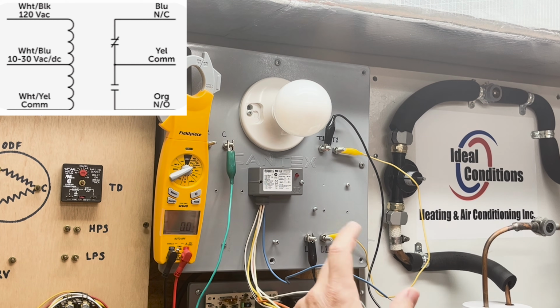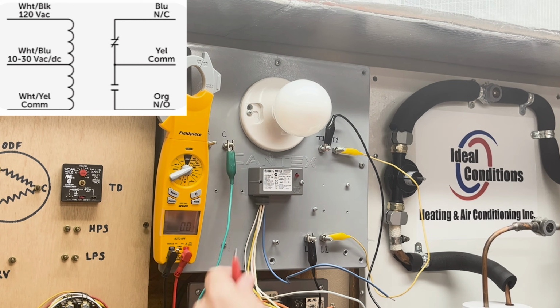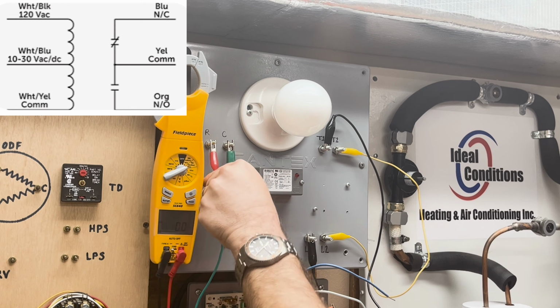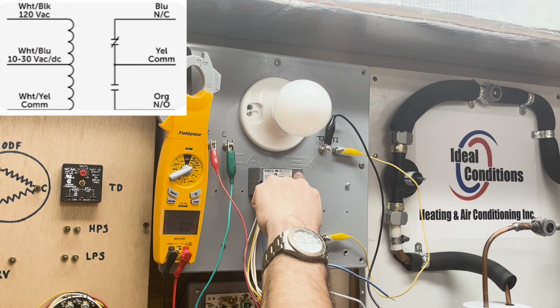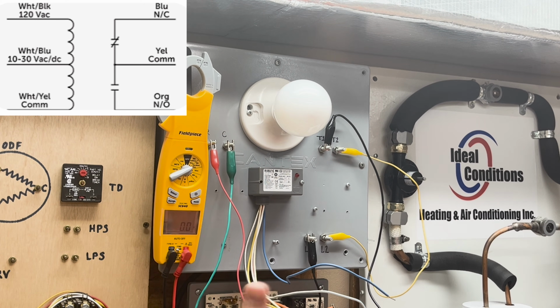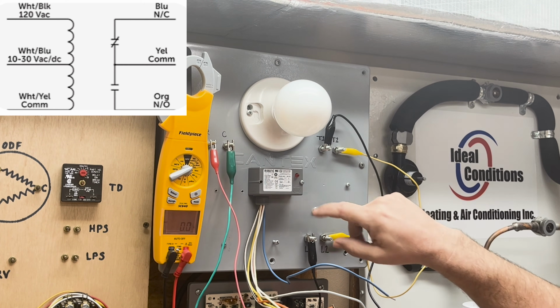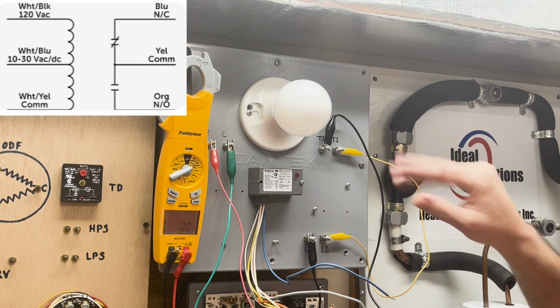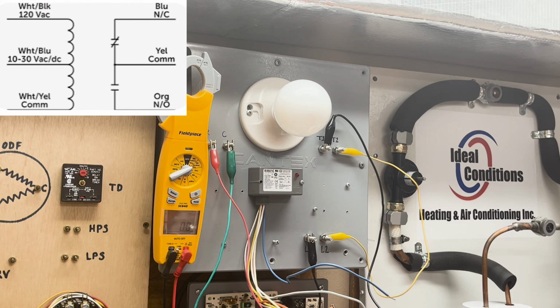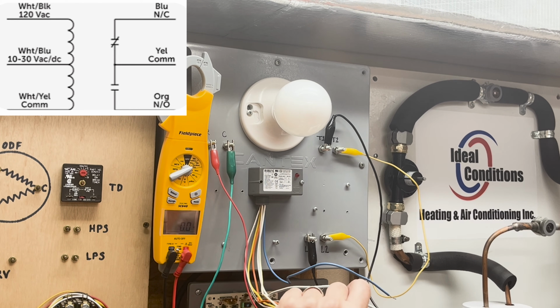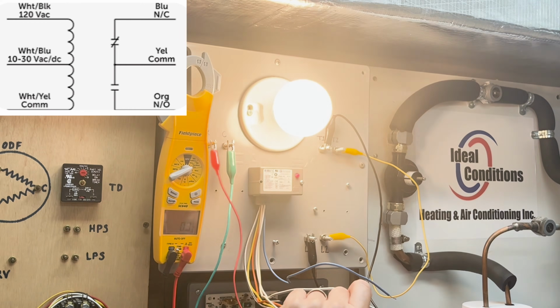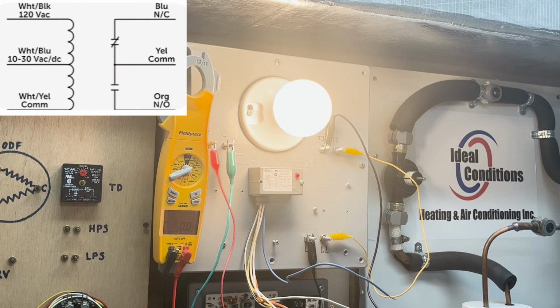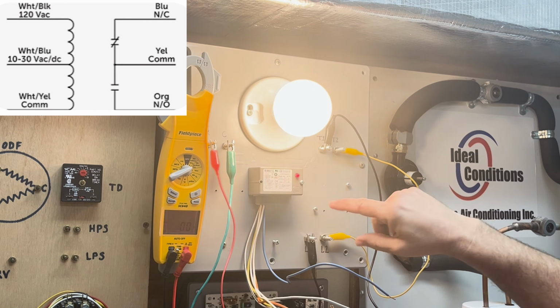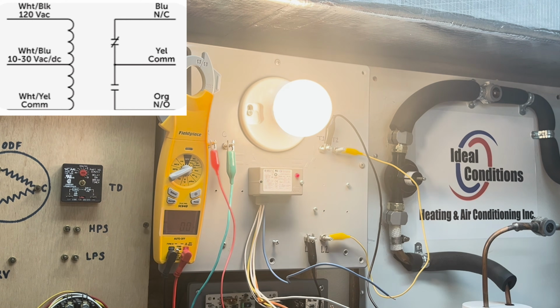Okay, I have two more wires. I can only pick one. That white/blue will be my 24 volt side, so we're going to go ahead and connect to that. You'll notice the red light will come on because, again, we're energizing the coil, but this time our load will activate because right now it's in the normally open and we already have that part wired up. So we're going to go to white/blue, give it 24 volts, and now you see the load came on. It was wired to normally open, and again our red light came on because it was for coil.